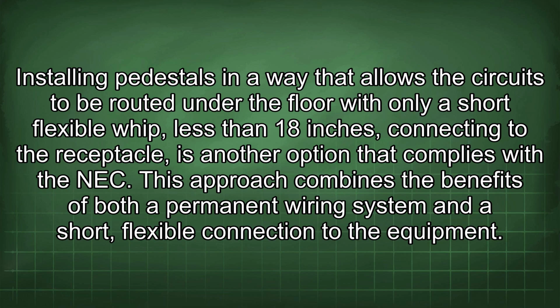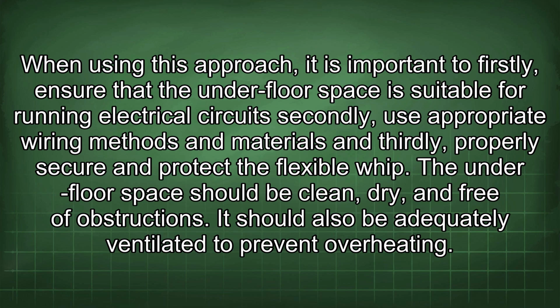Installing pedestals in a way that allows the circuits to be routed under the floor with only a short flexible whip, less than 18 inches, connecting to the receptacle is another option that complies with the NEC. This approach combines the benefits of both a permanent wiring system and a short, flexible connection to the equipment. When using this approach, it is important to firstly ensure that the underfloor space is suitable for running electrical circuits. Secondly, use appropriate wiring methods and materials. And thirdly, properly secure and protect the flexible whip.